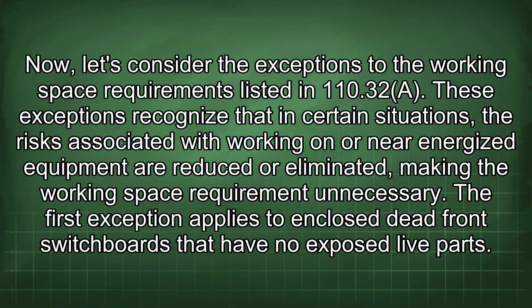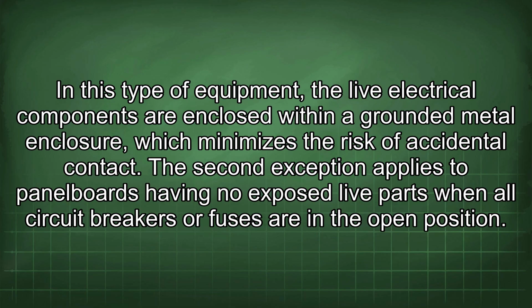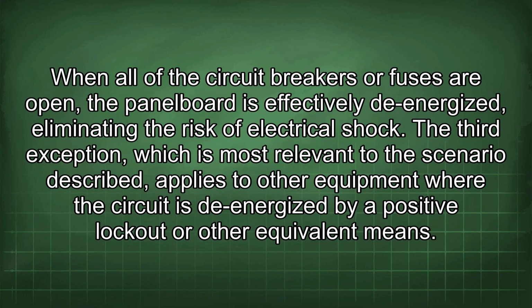The first exception applies to enclosed dead front switchboards that have no exposed live parts. In this type of equipment, the live electrical components are enclosed within a grounded metal enclosure, which minimizes the risk of accidental contact. The second exception applies to panel boards having no exposed live parts when all circuit breakers or fuses are in the open position. When all of the circuit breakers or fuses are open, the panel board is effectively de-energized, eliminating the risk of electrical shock. The third exception, which is most relevant to the scenario described, applies to other equipment where the circuit is de-energized by a positive lockout or other equivalent means.